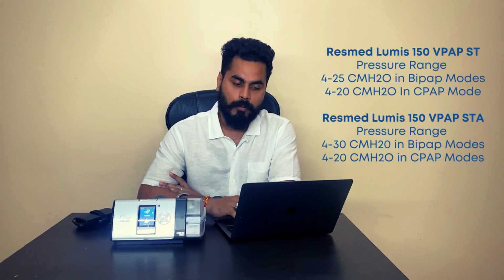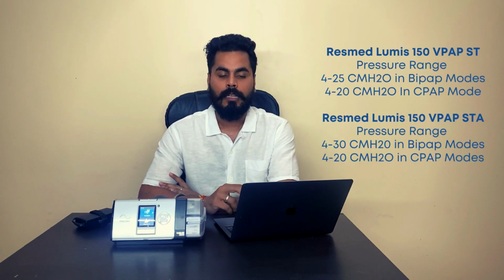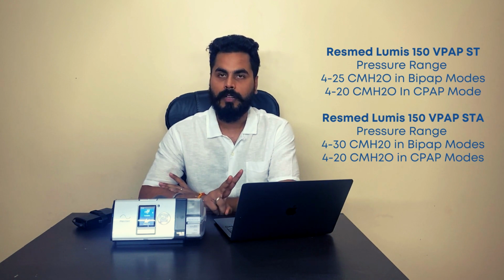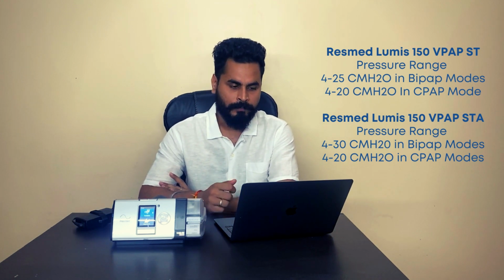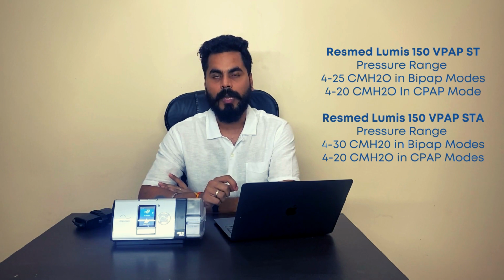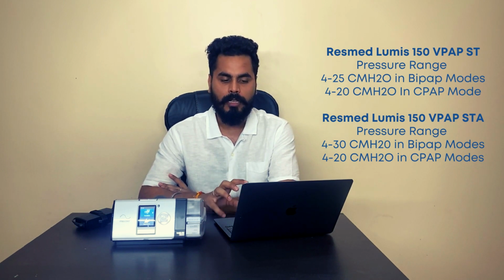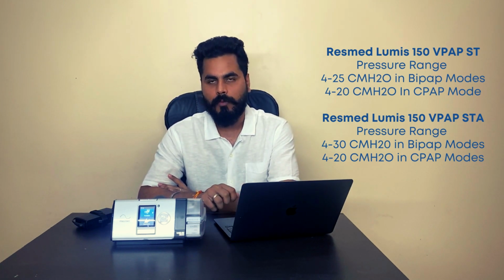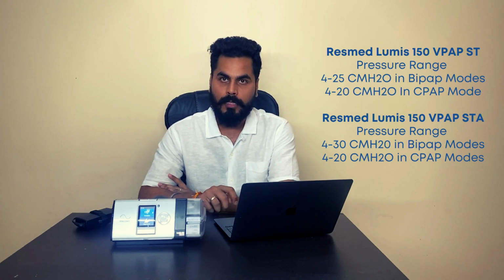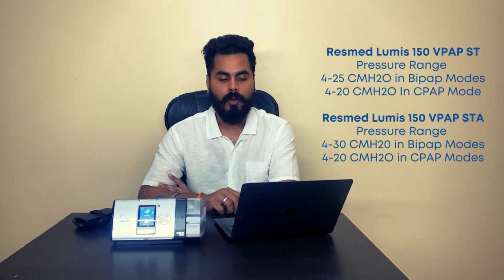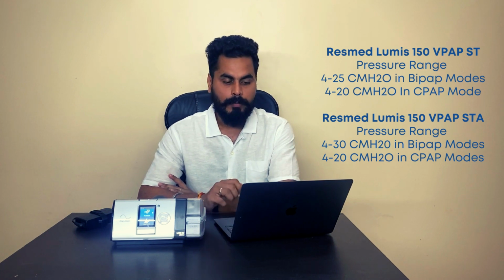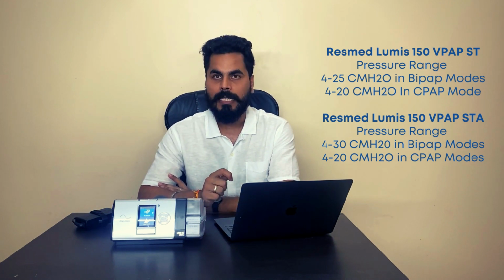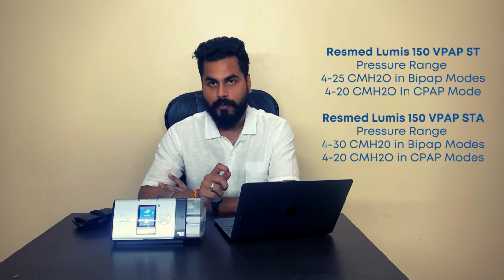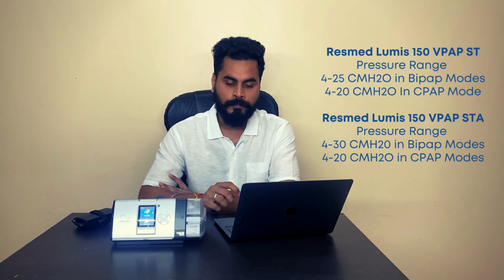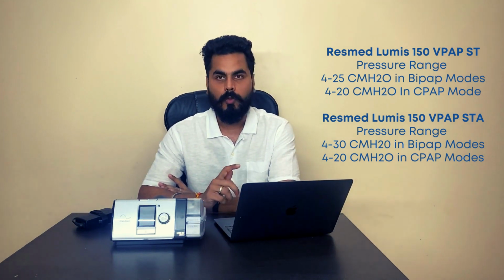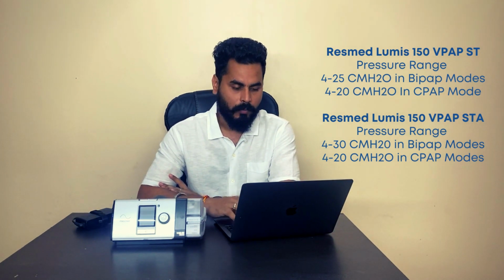Now, if we talk about the pressure range of this device, both variants have different pressures. So I'll explain it to you. The Resmed Lumis 150 Vpap ST model has a pressure range of 4 to 25 centimeter of water in Bipap modes and 4 to 20 centimeter of water in CPAP mode. The Resmed Lumis 150 Vpap STA model has a pressure range of 4 to 30 centimeter of water in Bipap modes and 4 to 20 centimeter of water in CPAP modes.